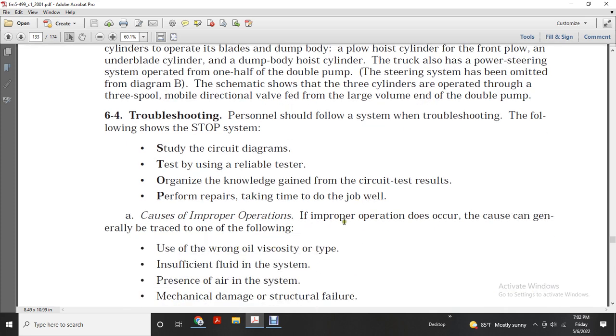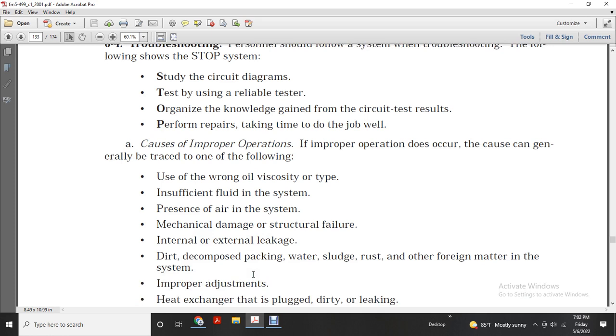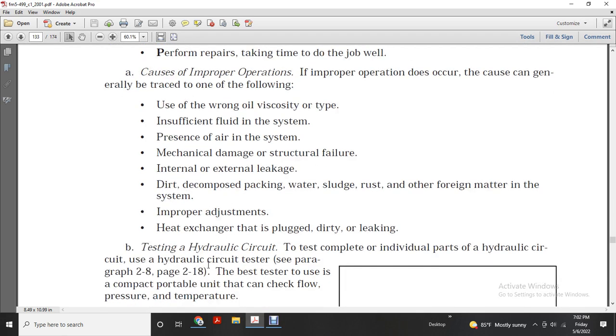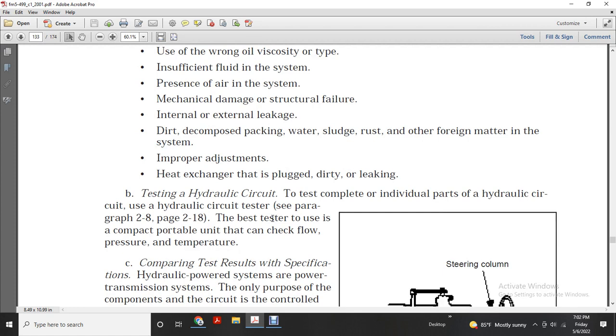Causes of improper operation: improper operation does occur, but the cause can generally be traced to one of the following: using the wrong type of oil, insufficient fluid in the system, air present in the system, mechanical damage, structural failure, internal or external leakage, dirt, decomposed packing, water, sludge, rust or other foreign material in the system, improper adjustment, a plugged heat exchanger, dirt, and leaks. Testing the hydraulic system means testing the individual parts of the hydraulic circuit.